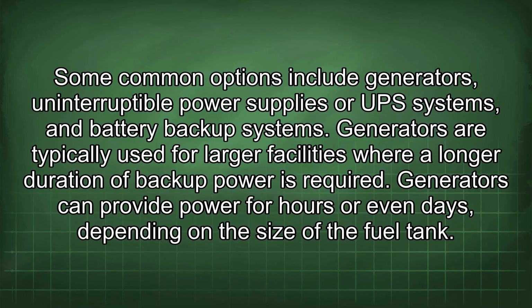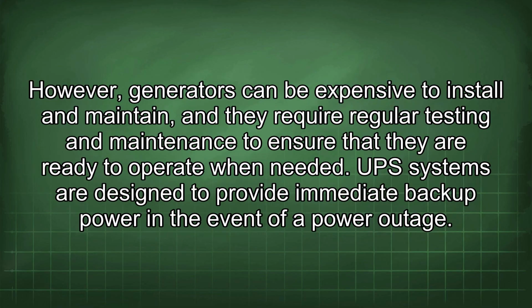Generators are typically used for larger facilities where a longer duration of backup power is required. Generators can provide power for hours or even days, depending on the size of the fuel tank. However, generators can be expensive to install and maintain, and they require regular testing and maintenance to ensure that they are ready to operate when needed.